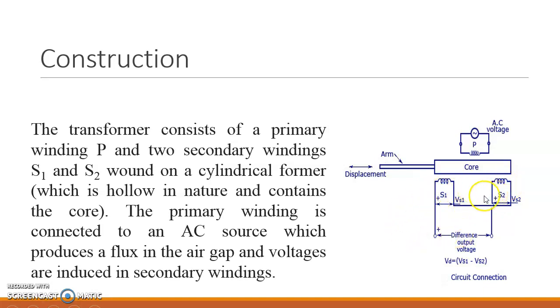The soft iron core, the center part, is made up of high permeability nickel iron, which is hydrogen annealed. It is hydrogen annealed so that the device has low harmonics and high sensitivity. The entire assembly of the LVDT is placed in a stainless steel housing, which provides electrostatic and electromagnetic shielding. Due to the shielding, the LVDT working is not affected by any stray magnetic field.